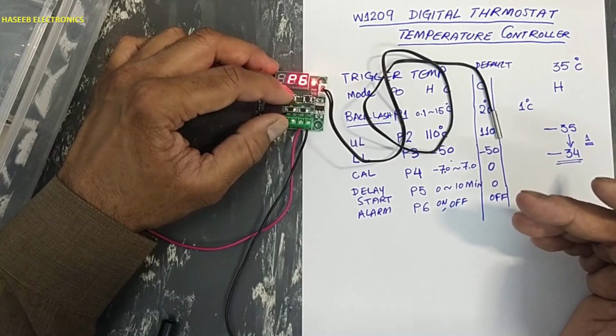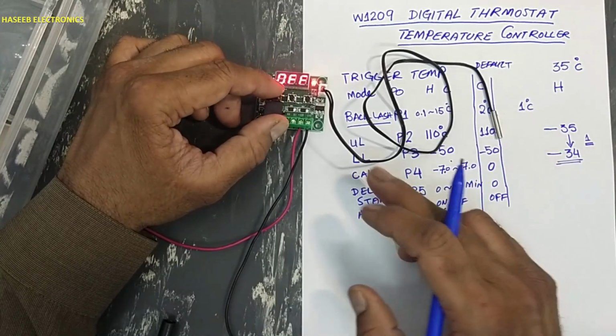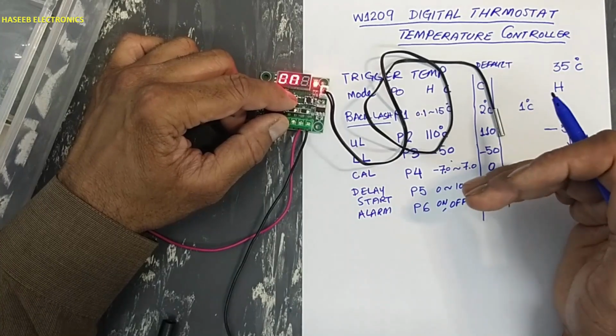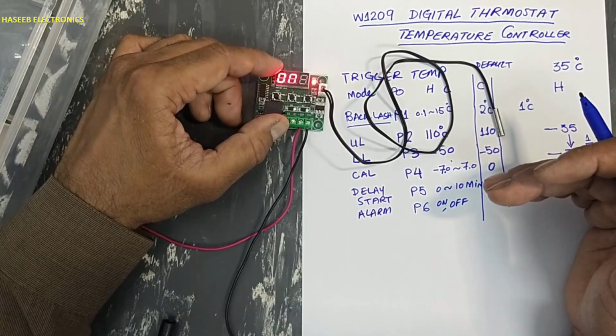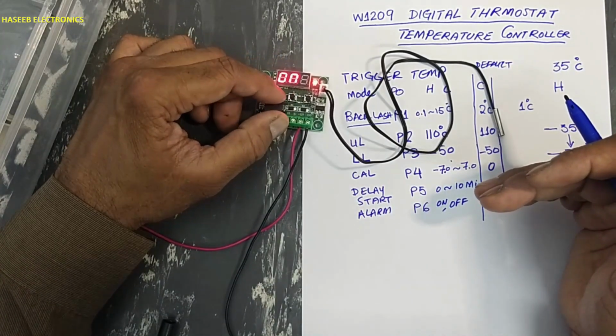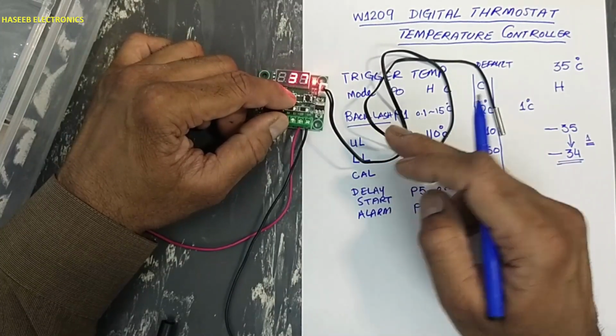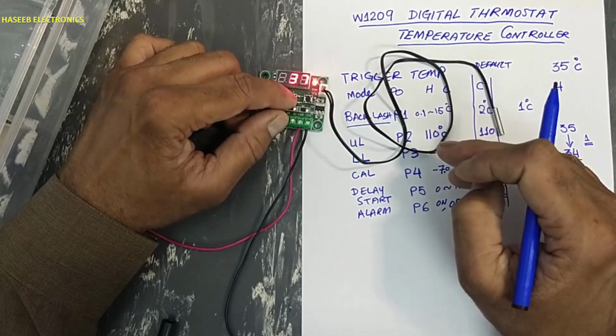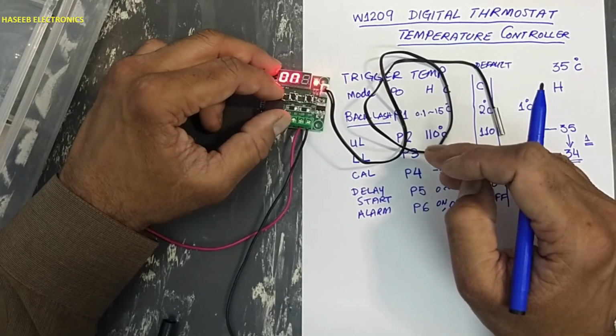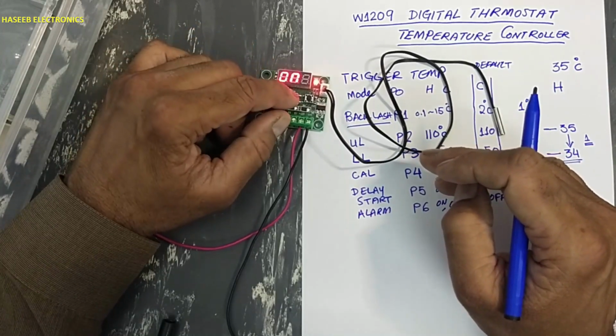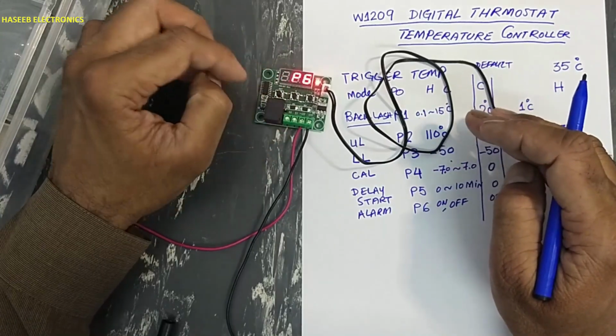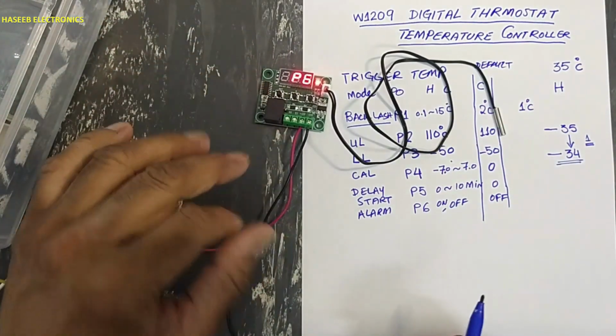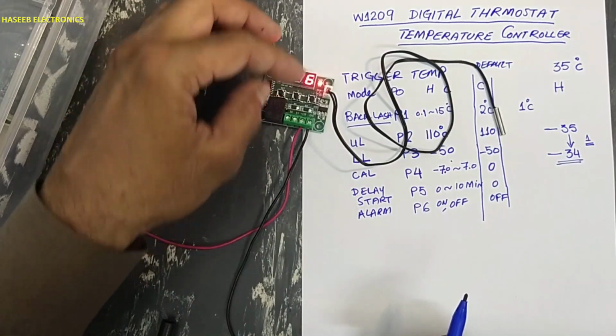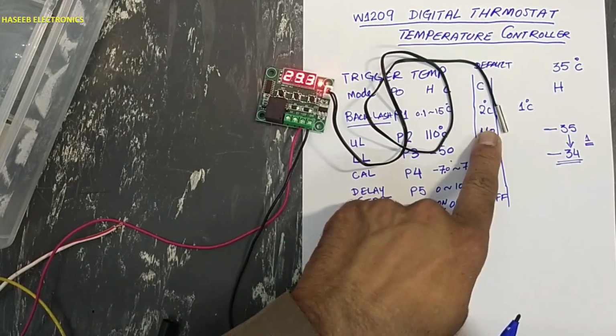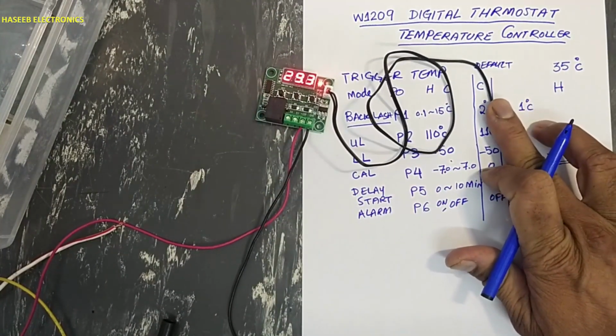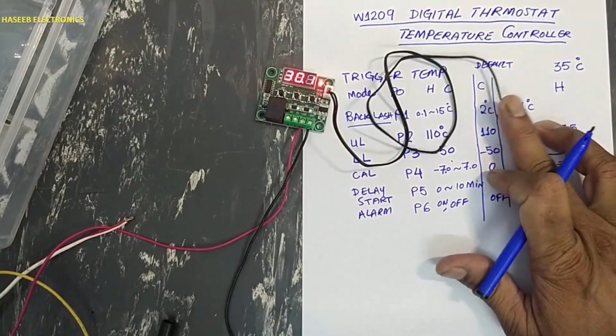Set P6. Set. Alarm is now off. If we want to set alarm, on. After on, it will enter into temperature. How much the top limit we want to set? We can say we don't want to set temperature, keep it off. Now leave it. It will store the value and it will now reach to this thermostat mode. This time it is showing the temperature here of this temperature sensor.